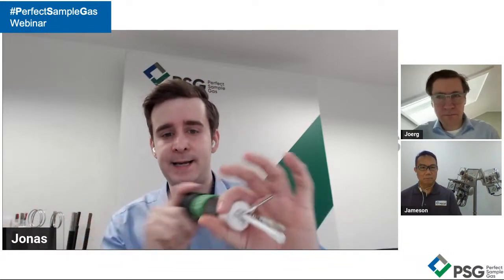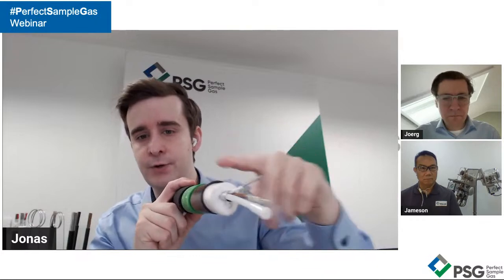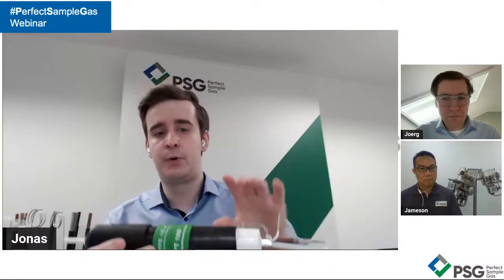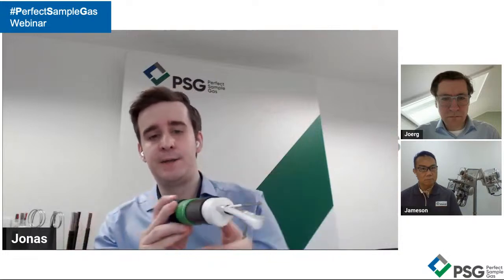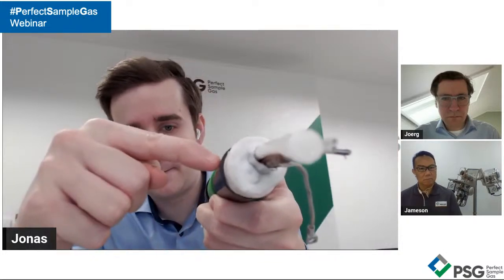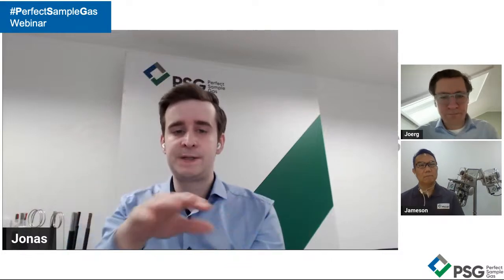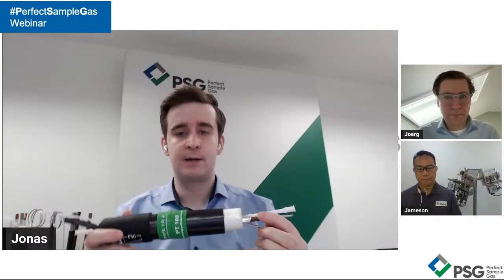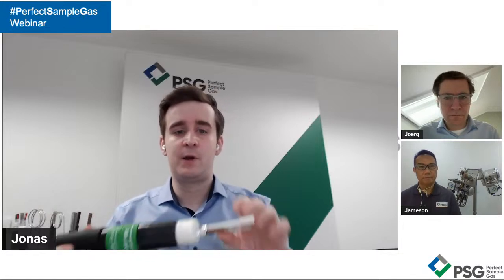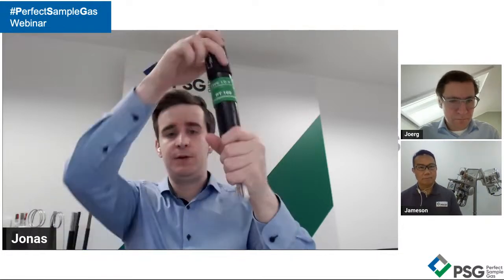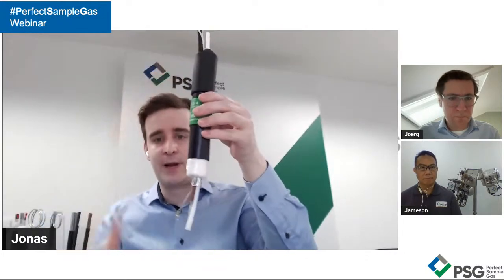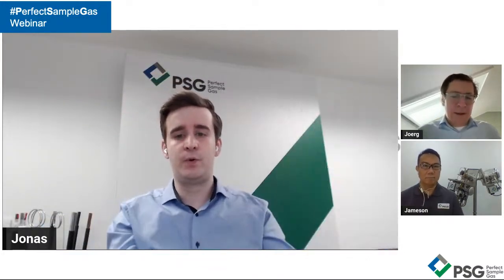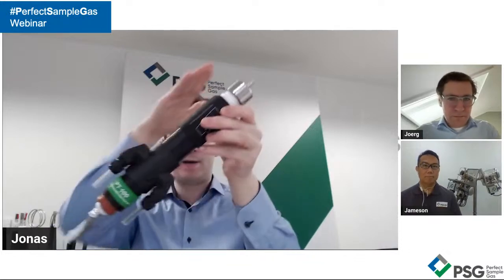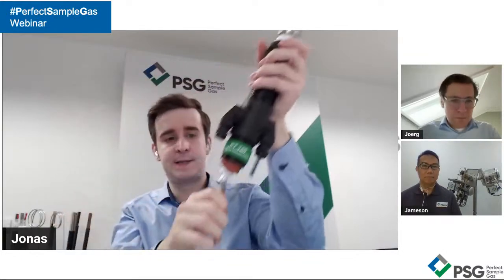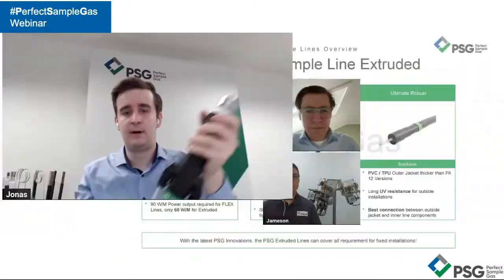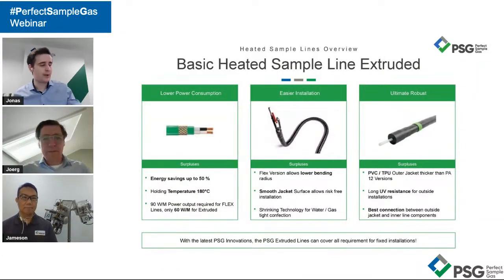Overall, this line is more energy efficient than the other one, just because of how it's mechanically made. It has a dense layer of insulation around it, then we put it into a machine that forms a layer of PVC on the outside. So it's a mechanically made product. Another great advantage is that because it's so densely packed, you can install it straight to the ground, whereas with the other type you'd always have to lay it in little loops, otherwise the tube would lengthen itself and cause a problem.